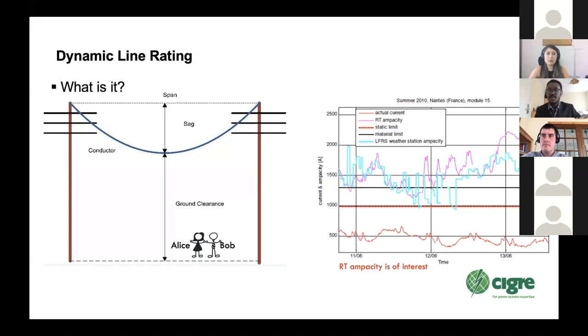However, what dynamic line rating, and this is the ingenuity of it, seeks to do is to monitor the actual weather conditions or line conditions alongside the entire line. And by doing this, if we know what the actual weather conditions along the line are, we can determine the amount of current that can be passed through the line without violating the ground clearance limitations.